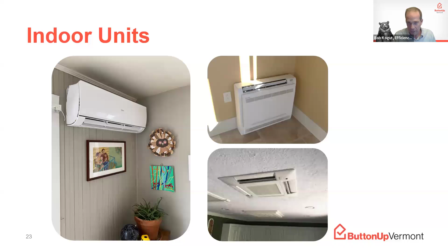A ductless heat pump, or mini split, is typically the least expensive way to get into using a heat pump. They're relatively fast and easy installations because they don't require a distribution system — you don't have to hook them up to ducting, radiators, or piping throughout your house. You just need to mount the indoor unit somewhere. Refrigerant piping, typically just 2 copper pipes with insulation around them, gets run outside, and you need to set that outdoor unit somewhere — it can be bolted to the outside of your house, on a concrete pad, or sit outside in other ways.